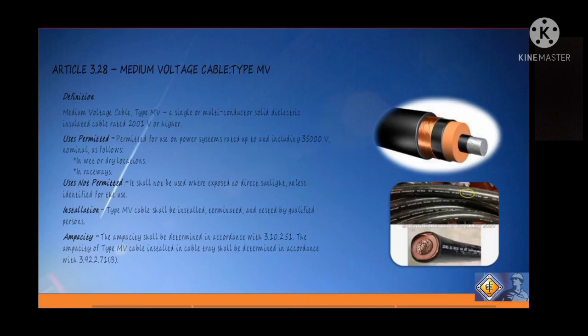Next, in Article 3.28, which is the medium voltage cable, or the type MV. Medium voltage cable is a single or multi-conductor solid dielectric insulated cable rated 2001 volts or higher. Makikita na natin sa right slide ulit ng ating slide yung itsura ng ating type MV or the medium voltage cable. In terms of use permitted naman, it is permitted for use on power rated up to and including 35,000 volts nominal, as follows: in wet or dry location and in a raceway.